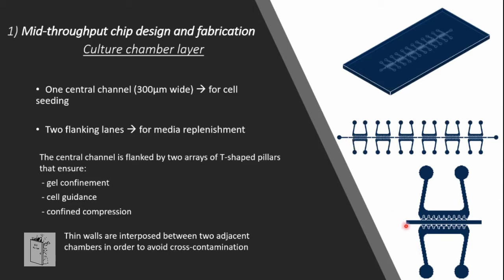Each chamber has three different channels: the central one where cells are seeded with hydrogel, and two flanking lanes for media replenishment. The peculiar characteristic of this cartilage-on-chip device is that it also features two arrays of pillars, which are important for gel confinement, cell guidance, and exerting confined compression — the final aim of the work.